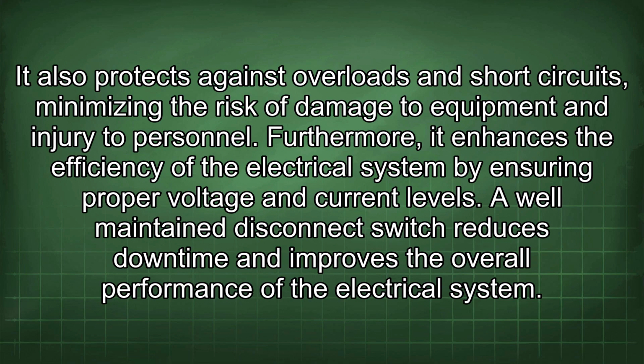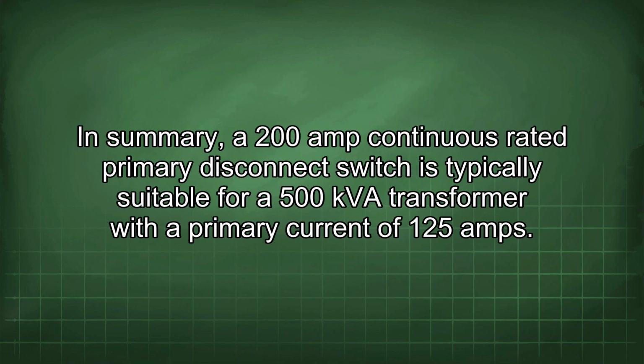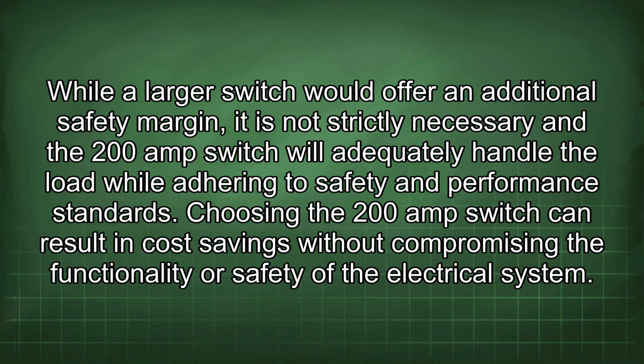Furthermore, it enhances the efficiency of the electrical system by ensuring proper voltage and current levels. A well-maintained disconnect switch reduces downtime and improves the overall performance of the electrical system. In summary, a 200 amp continuous rated primary disconnect switch is typically suitable for a 500 kVA transformer with a primary current of 125 amps. While a larger switch would offer an additional safety margin, it is not strictly necessary, and the 200 amp switch will adequately handle the load while adhering to safety and performance standards.